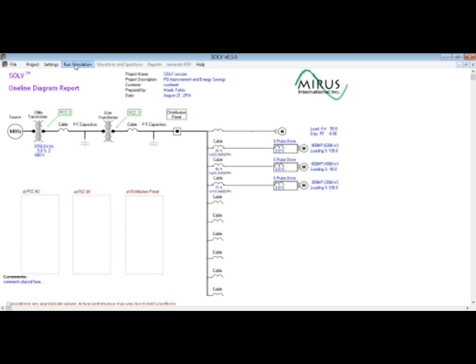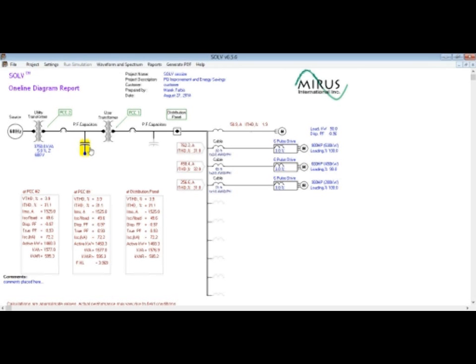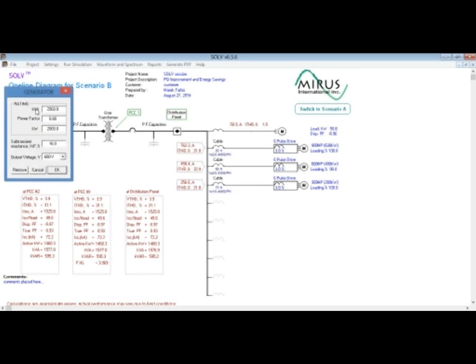So I run the simulation now, and after calculations are finished, each drive load branch draws current above 31% THD, and the voltage distortion in the system is below 4%. Please note that the ratio of the short circuit current to the load current, ISC to I load, is about 50, 49.6 to be exact. So let's create a second scenario and change the source, the utility transformer, to a generator, with typical 16% subtransient reactance and 2500 kVA size.